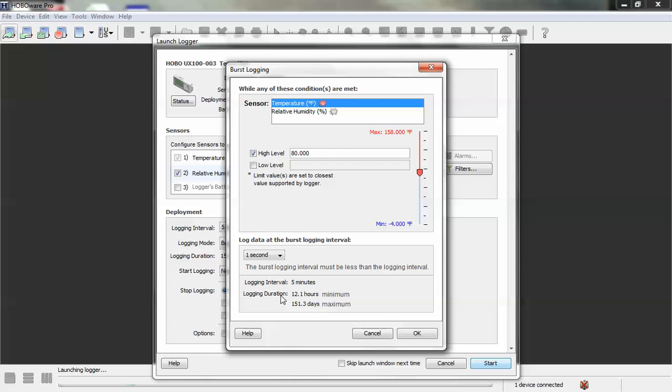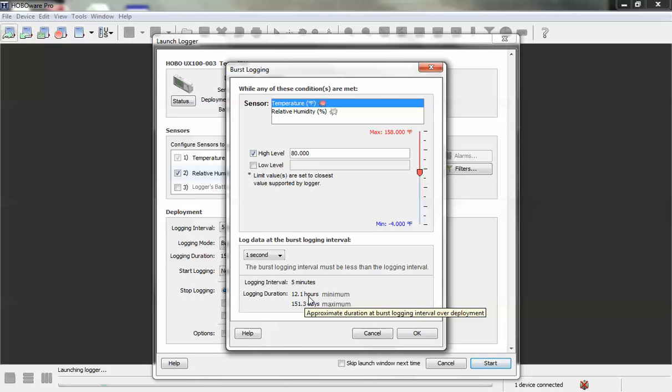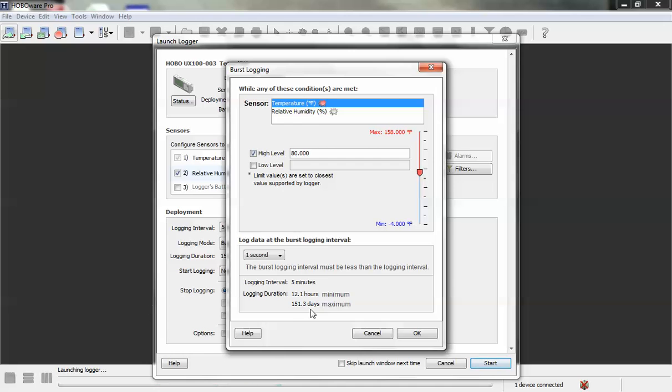Here it gives you the calculated logging duration. HoboWare is giving us the calculated logging duration based on a minimum and a maximum. The minimum being if the logger was in alarm or the temperature was above that threshold all the time, it would log for 12 hours. If it never goes above 80 degrees, it will log for 151.3 days.